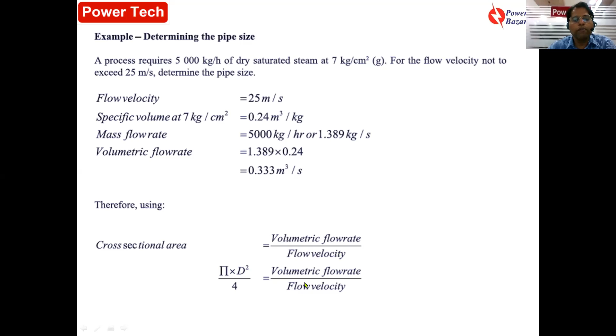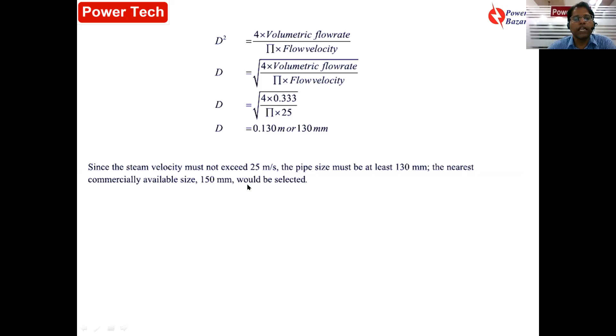Now, since steam flow velocity must not exceed 25 meter per second, you don't have a pipe size of 130 mm. The nearest commercially available pipe size is 150 mm. We cannot go for a 100 mm pipe size because the steam velocity would be more than 25, and it should not exceed 25 meter per second. So in this case, the pipe size that needs to be selected is 150 millimeter.